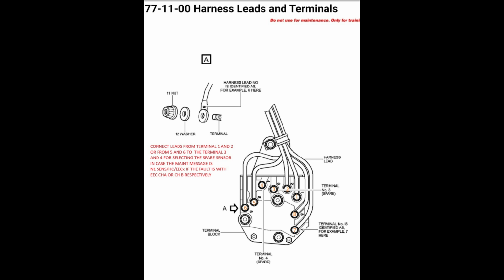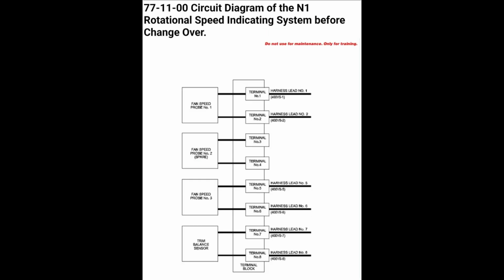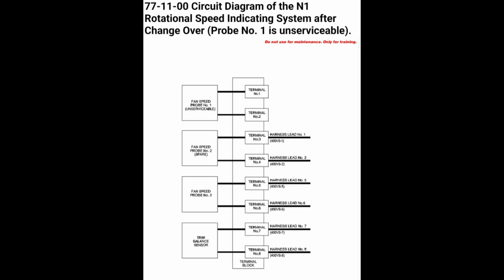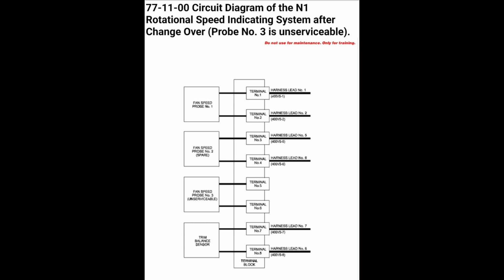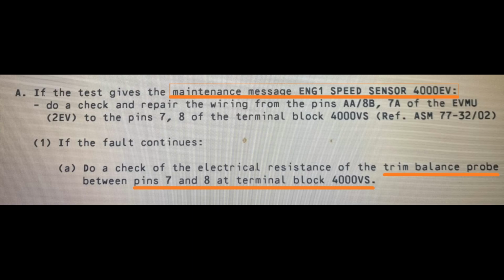If you look at the circuit diagram of the N1 rotational speed indicating system before the changeover, the sensors are connected to the normal connections. Suppose sensor 1 fails. Sensor 1 failing means EEC channel A is registering the fault. Then you have to change number 1 to terminal numbers 3 and 4. If channel B is having a problem, then the number 3 probe has to be changed to the spare connection 3 and 4 on the terminal block. We can have a different fault also, for the trim balance sensor. For the trim balance sensor you will get the fault engine 1 speed sensor 4000 EV.